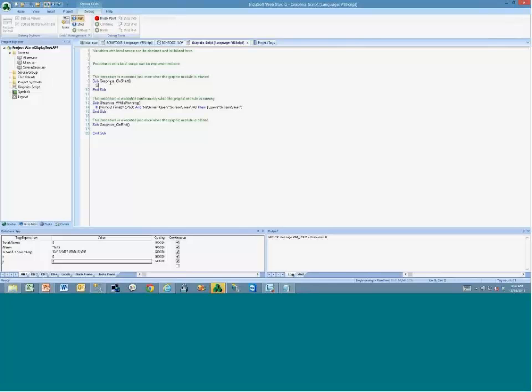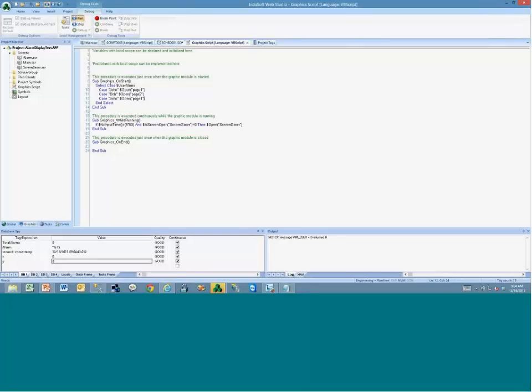So here you can have something like select case and use the local tag username, right? And select, and you say case John is logged. Then you open, like you wrote, page 1. Case Bob, open page 2. Case Mike, open page 3. And it's always good to have a case else. Open, let's say, home, whatever it is. So every time that the viewer starts on each one of the thin clients, based on the value of the username, you open each one of those different screens. Clear?